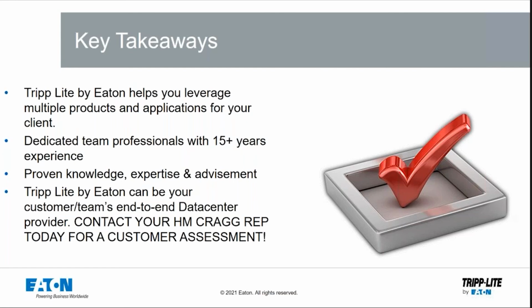What I want to relay to you is a typical design or scenario from this standpoint. We get a lot of emails -- I deal with about 20 to 30 of them a day myself, not personal, just inbound calls, etc. All of them revolve around the experience of 'I need this, I need this, I need this.' From an aspect of single phase and UPS system design, which is kind of my bread and butter, I can tell you 50% of the projects that come into me may not have customer eyes on them in terms of power requirements to a UPS -- simplified things you'd think are rather easy. And 50% of those projects likely get changed or altered to some degree to better satisfy the customer's requirements. Most of these things are basically pre-spec'd out.